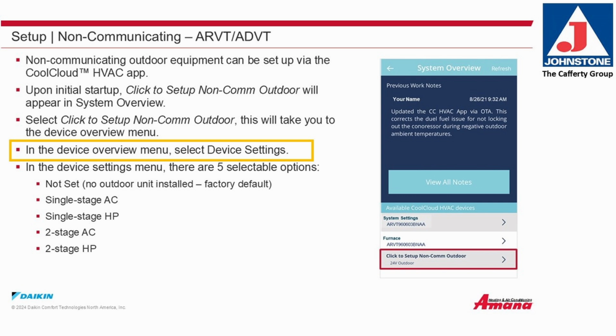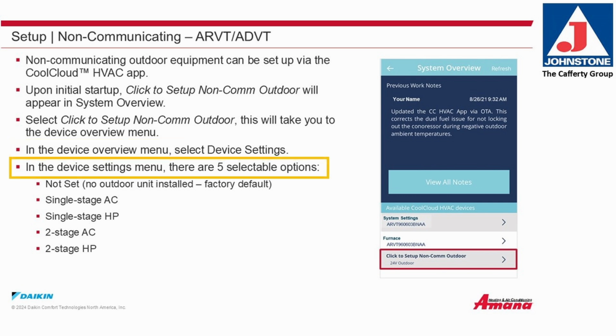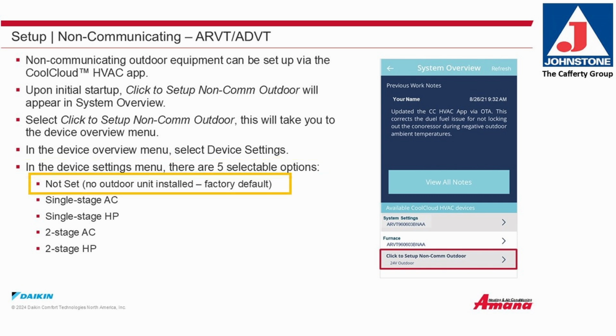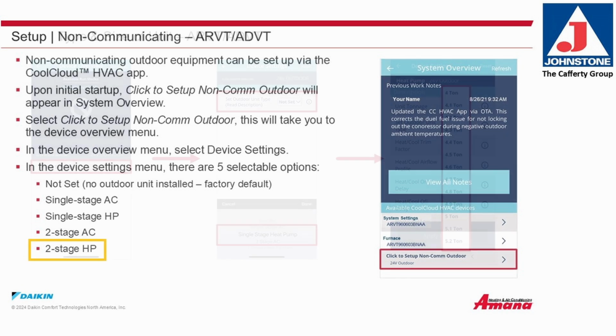In the device settings menu, there are 5 selectable options. Not set, meaning no outdoor unit installed. That is the factory default. Single stage AC, single stage heat pump, 2-stage AC, 2-stage heat pump. Set up the type and size of the unit.